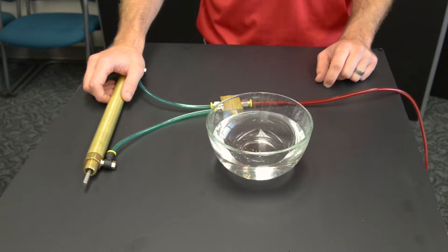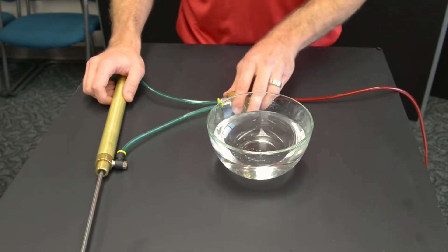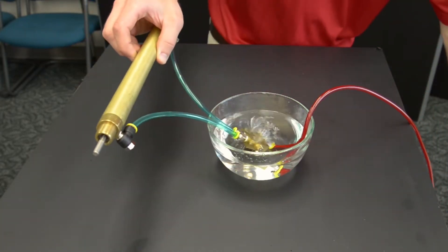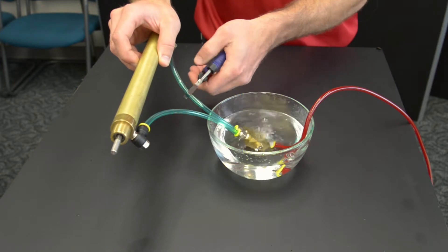Pressurize your system and cycle the valve until it is in the position where the leak is coming out of the exhaust port. As the leak is occurring, pinch the line closest to the exhaust port leaking.